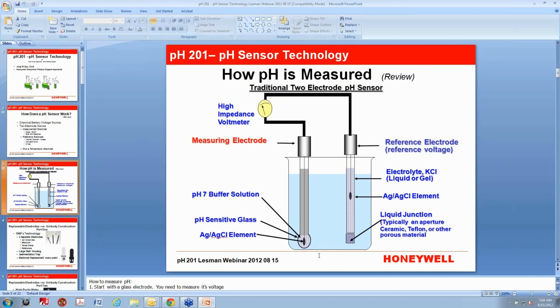So as this is changing, the signal goes to your transmitter or your analyzer, and we call that a high impedance voltmeter. You can't just hook a pH sensor to a millivolt source, like a multimeter, and try to read it, because it's a very high impedance measurement. It has a lot of resistance in that glass, and you only have picoamps of current flowing, so you get a little current loss. You don't get the right signal. So that's why you have to have a pH analyzer or a pH transmitter.